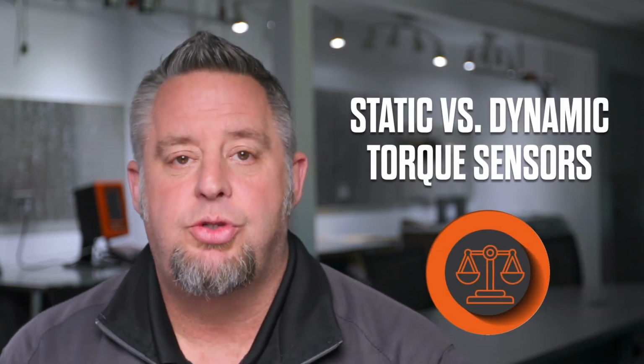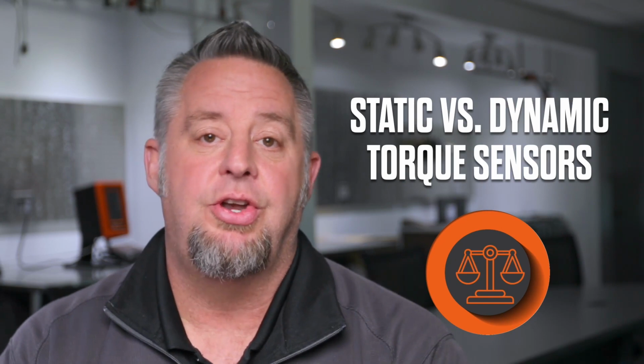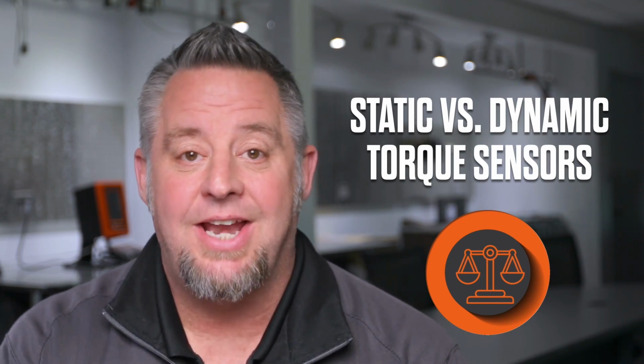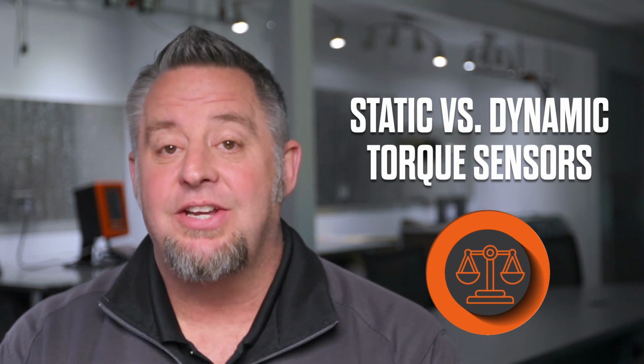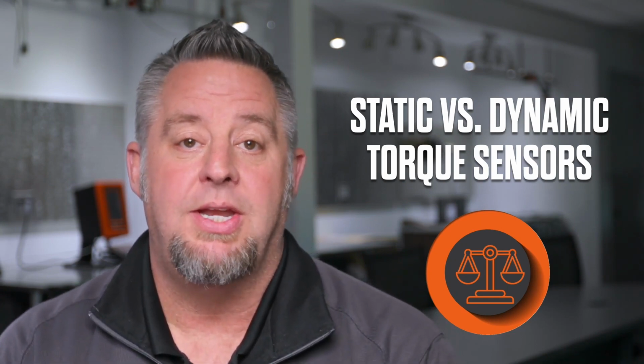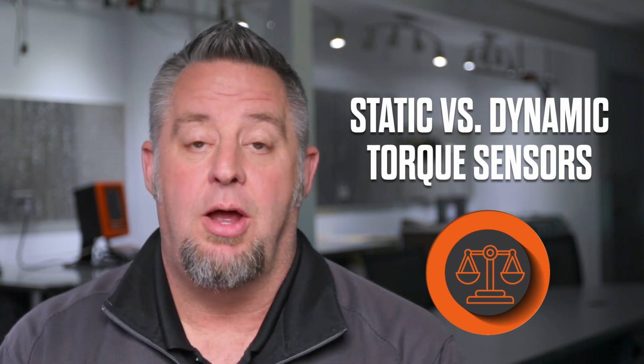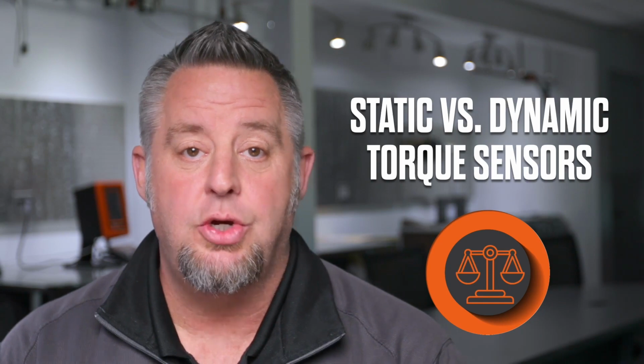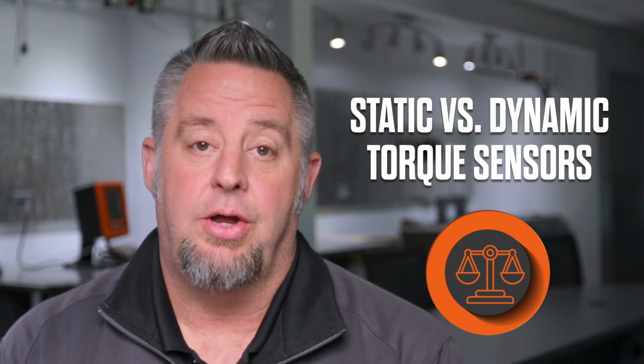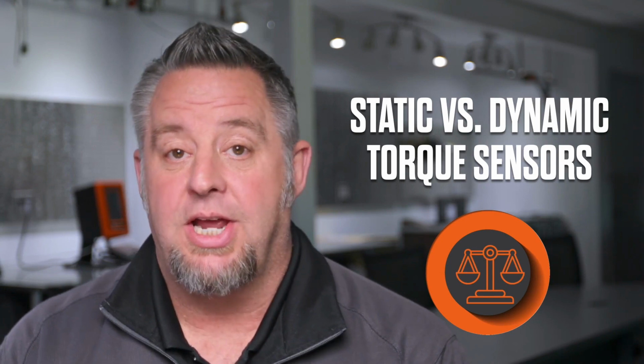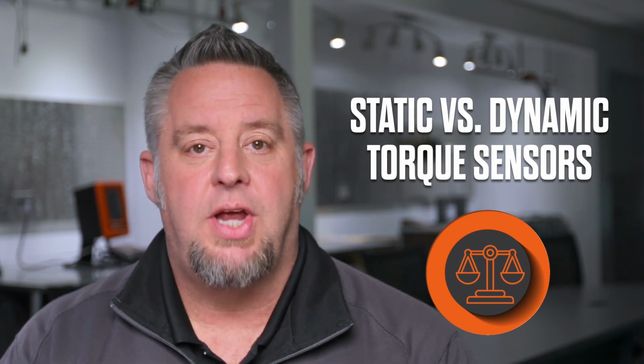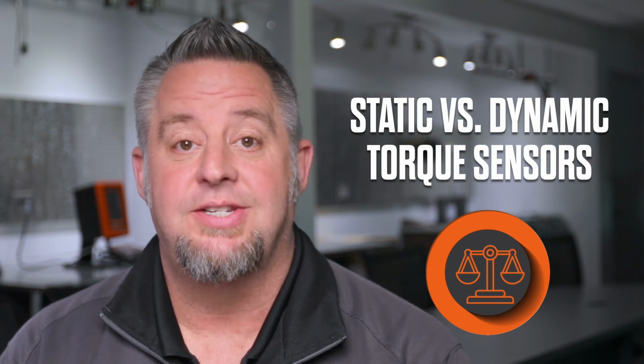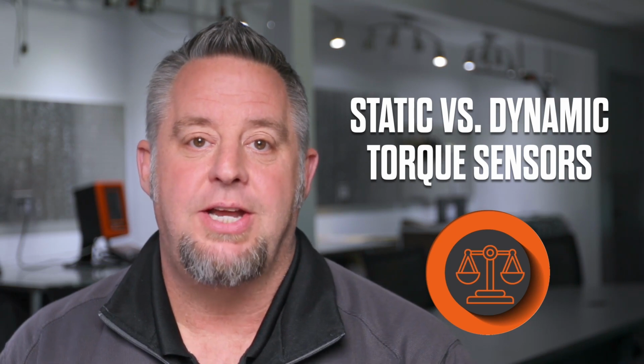All of that is to say that these are sensitive pieces of equipment that are calibrated to a certain standard using dead weights. Now there are two basic standard torque sensors. That's going to be a static sensor and a dynamic sensor. The static sensor is basically measuring torque at one moment in time. A dynamic sensor can be measuring as a tool is in use during a particular tool rundown or application. So this will be a little bit more clear to you as we look at the sensors during the little demo portion of today's presentation.